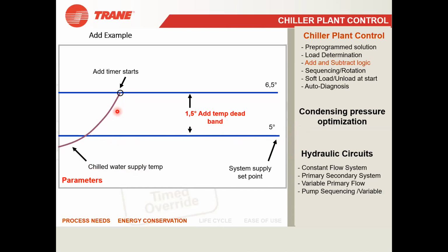Suppose it is fluctuating. It is going there and then again coming back. So whenever it reaches this dead band, you can see 6.5 degrees, it always starts the timer. And recording will be started, so that you can visualize or see that something is happening in the office, because the office may be having more people. That's why, sitting in the control room, you can see all these things. And then again it is fluctuating. Whenever it reaches this 6.5 degree band, it starts the timer, but it has not yet started another chiller.